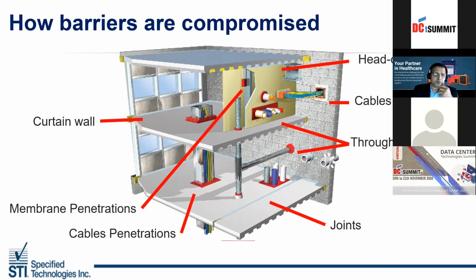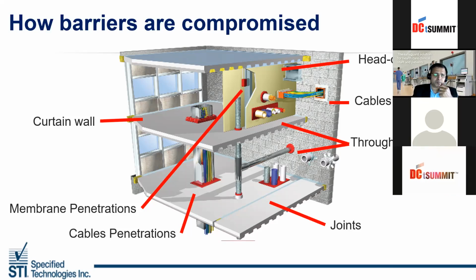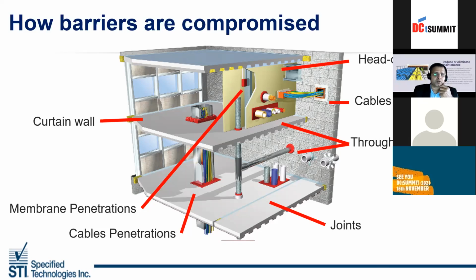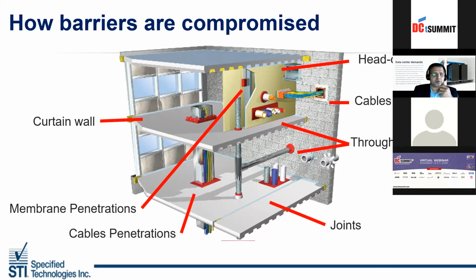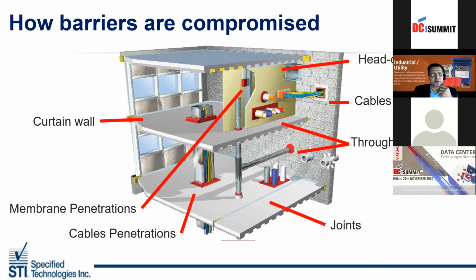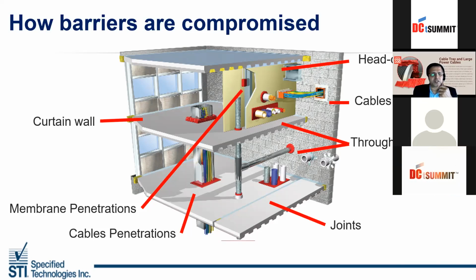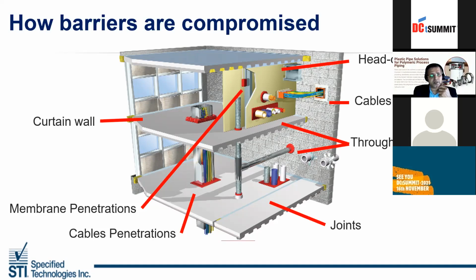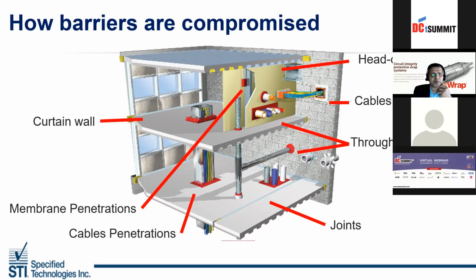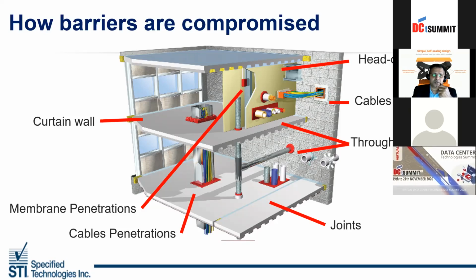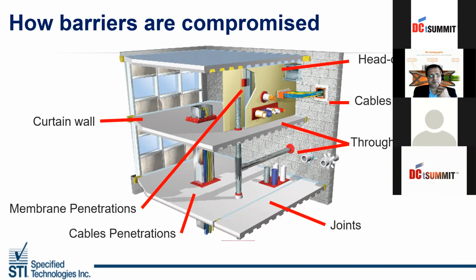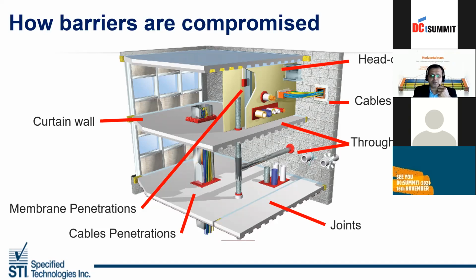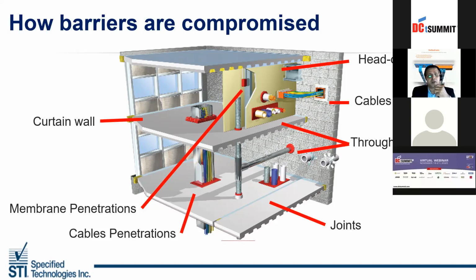Normally in every project there is a certain amount of gap provided in a building to adjust to the environmental changes or the additions of manpower and furniture which keep on adding. So this joint acts as a dynamic joint which supports the undulations happening, or in case of fire it'll act as a fire and smoke barrier also. Through penetrations to your walls, concrete walls, block walls, and fire-rated gypsum walls, and head of wall joints. As I mentioned, there are different joints like wall to wall, head of wall, floor to floor joints. So all these joints also have to be catered to and done as fire stopping for these areas also.